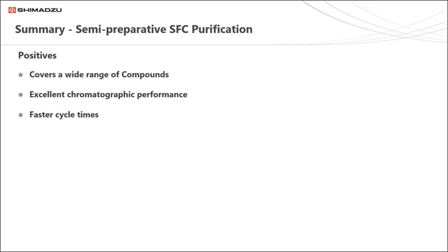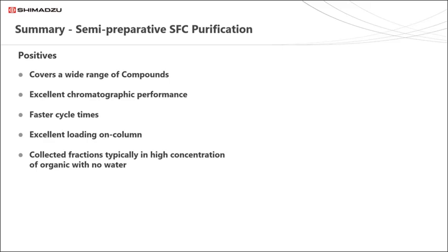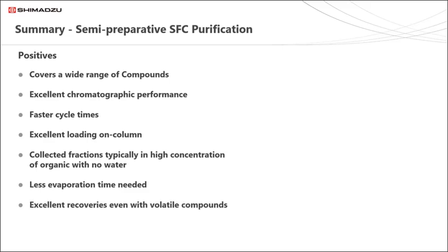Typically faster cycle times, excellent loading on column, and the collected fractions typically are in a high concentration of organic with no water. Hence, less evaporation time is needed. Excellent recoveries also of very volatile compounds. And it's easy to clean and maintain its components.